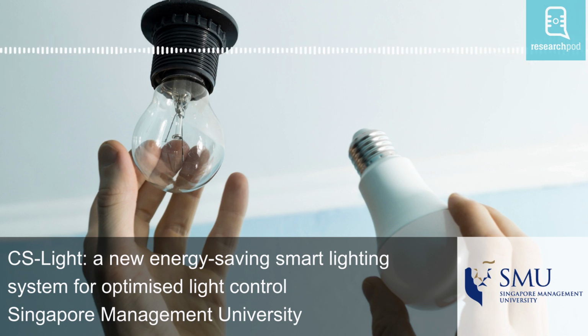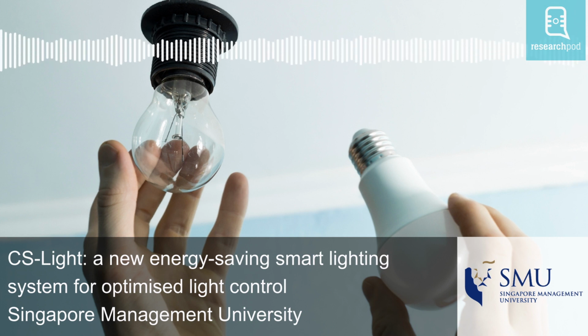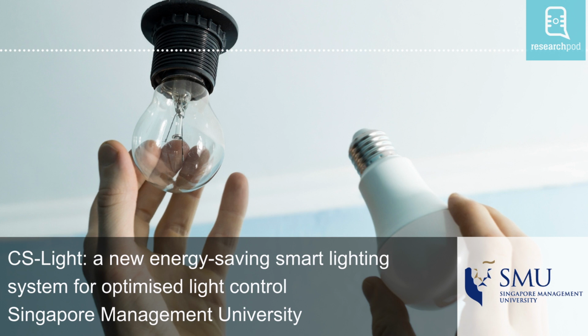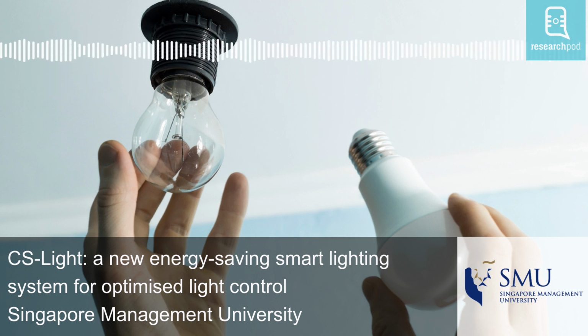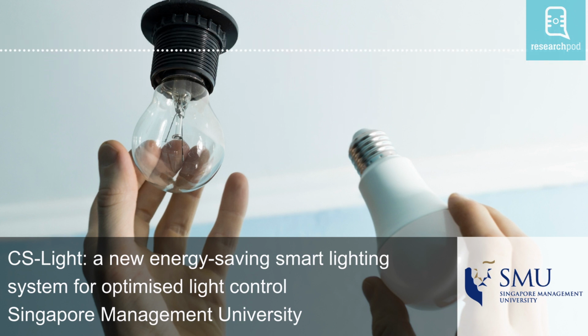The ML-based method used for estimating lux was demonstrated to be accurate, with a median error of 8.5% across different real-world conditions. The researchers showed that using CS-Light reduced lighting energy consumption by 53% under normal levels of human occupancy and during daylight hours. To ensure that CS-Light wasn't disruptive to the occupants, the team also asked 15 individuals to provide their responses to a survey of comfort and operability while CS-Light was in operation.